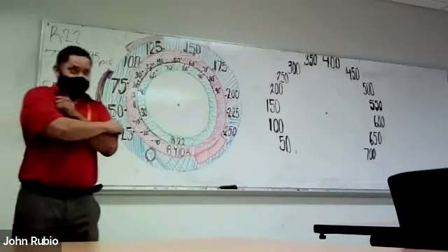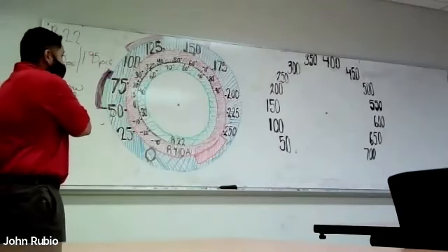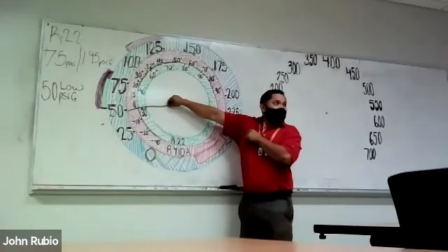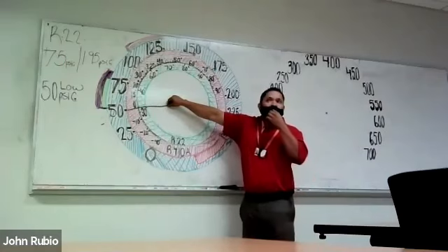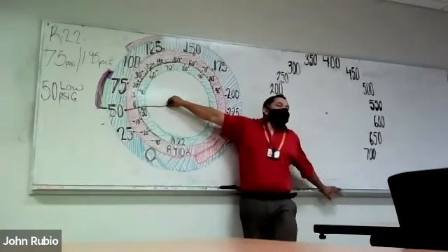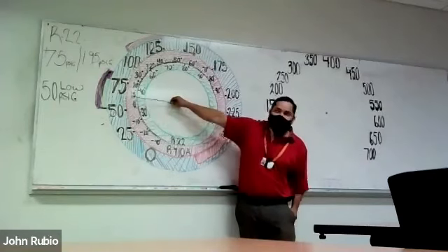This is drawn to scale. It took me like 4 minutes to draw all the scale yesterday. So when I hold my needle at 50, if you look at your gauges, you will find a similar orientation. Look at your green bar when your PSIG is 50. Look at your outer line, and imagine your needle is sitting at that 50, and then follow the needle back. Where do you land on that green line? You land there? 32, 30. You see it? Right at 50 PSIG.